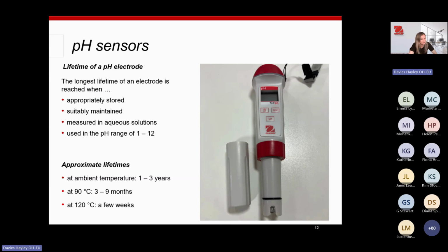So these are approximate lifetimes that are suggested for pH probes. If you are testing samples at ambient temperature, then the approximate lifetime suggested is between 1 to 3 years. If you are using your electrodes at up to 90 degrees, the lifetime of the probe will dramatically decrease down to around 3 to 9 months. And if you're using it at 120, it could be a few weeks.